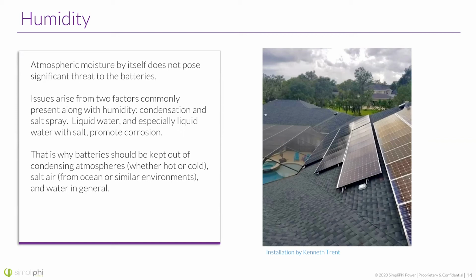Humidity itself is not a big impact. The liquid water itself would be. And then liquid water with salt. So salt spray. So again, if you're just living by the coast, we manufacture in California, maybe 5 minutes away from the beach, we're pretty close to the ocean there even. It's not about that as much as the actual liquid, the actual salt spray. So if that's going to happen direct to the battery, you might see some kind of promoted corrosion within the battery.